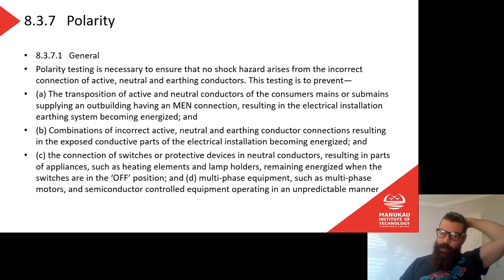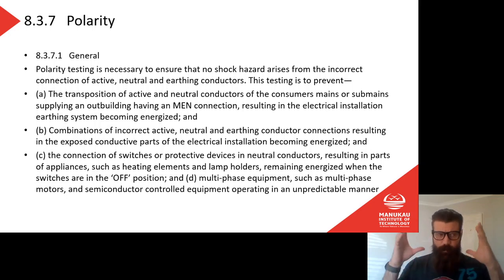So we need to always check, and this is part of our polarity testing, that our switches are switching in the phase conductor and not the neutral conductor. We will see this a little bit more. It's probably quite a difficult concept. Some of you will pick that up fairly easily and understand what I'm talking about. Some of you might find that quite hard to understand. We'll be able to see what that means when we do a bit more practical stuff. When we start getting into wiring up circuits, I'll be able to explain what I mean by putting the switch in the phase conductor and not the neutral.